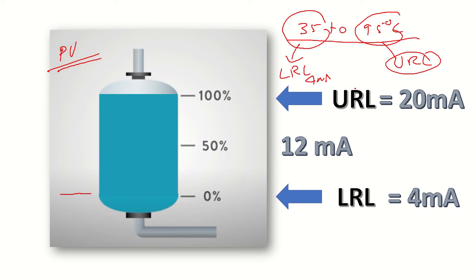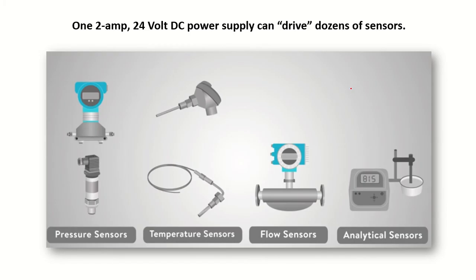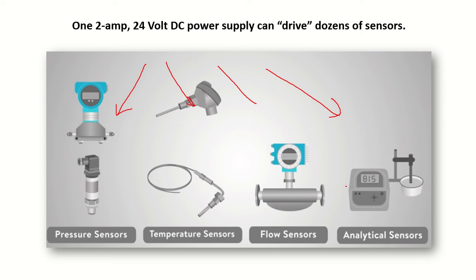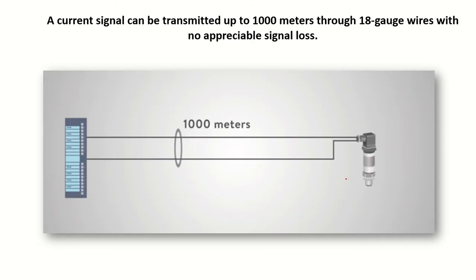A great advantage of using this 4 to 20 milliampere current loop is that a single 2-ampere 24-volt DC supply can drive dozens of sensors — pressure sensors, temperature sensors, flow sensors, analytical sensors. That is a very important aspect. Another important advantage is that data can be transmitted even for long distances, up to 1000 meters.